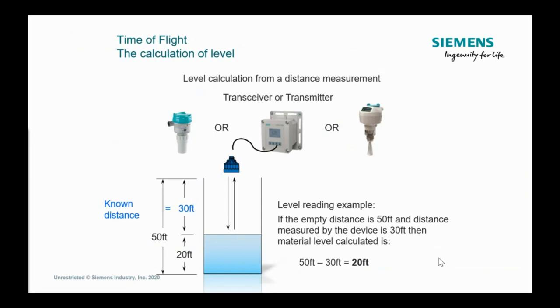The one caution I would give you though is if you're doing it in distance mode, or if you're switching back and forth between level and distance mode, if the instrument is acting weird, take a step back, take a deep breath, and ask yourself the question, am I in distance mode or am I in level mode? Because it happens to all of us, myself included. I'm thinking in my mind the instrument's in level mode and it's in distance mode or vice versa, and I'm getting really nonsensical information. That one can jump up and bite you. And I would contend that if anybody on the call here makes a mistake in the field that I haven't personally made already, you have accomplished something pretty special, because I have fallen into that trap a number of times. So if it's acting weird, take a step back and ask yourself the question, am I in distance? Am I in level mode?